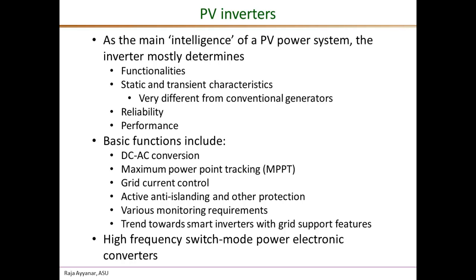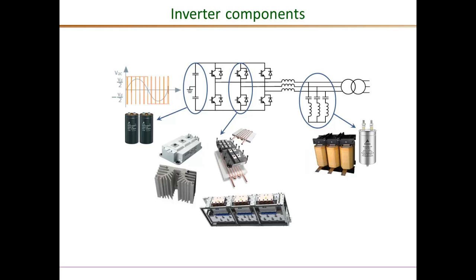It is important to remember that PV inverters are high-frequency switching power electronic converters. Some of the major components of an inverter are shown in this slide. These are switch-mode power converters with semiconductor switches that switch at fairly high frequencies in the 5 to 20 kilohertz range to produce the switching waveforms, which have the 60 Hz fundamental component that we essentially control to meet our control objectives. The switches are made of semiconductor devices with their heat removal mechanism.